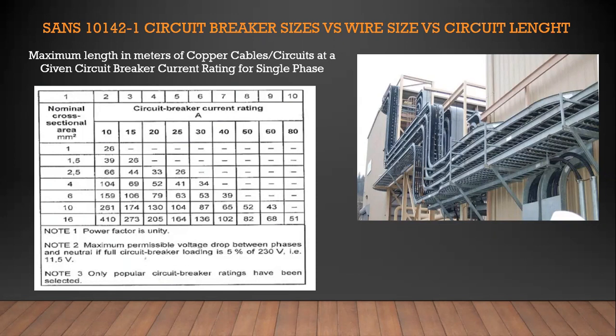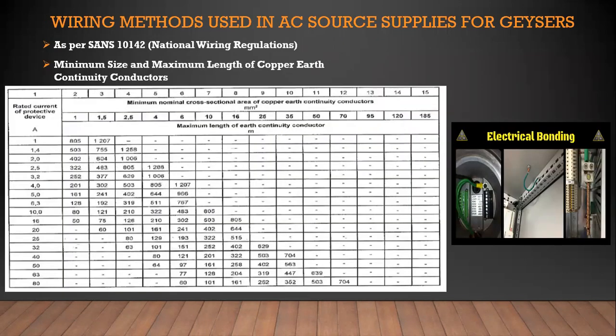With voltage drop problems come other problems like loose connections and wires getting hot, and that creates fire risks and damage to the installation and to property. We're also looking at the earth wiring, the maximum nominal cross-section of the copper earth continuity conductors. On the maximum amperage of the geyser circuit breaker, let's say it's a 20 amp, we've got a 2.5 millimeter wire in for the bonding and the earthing. The maximum distance that circuit could be is 101 meters. So this is a quick table for you to determine, is the installation looking okay or not?